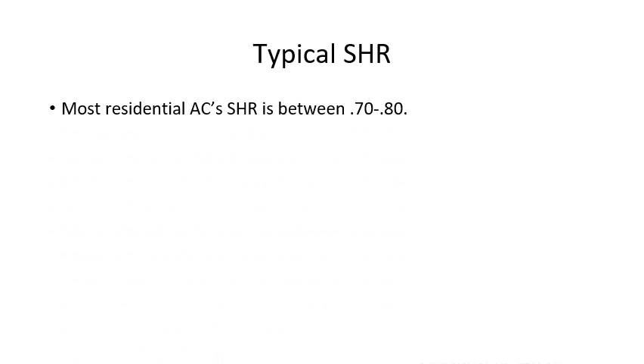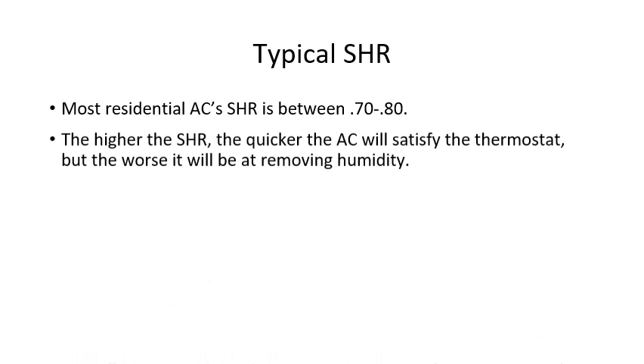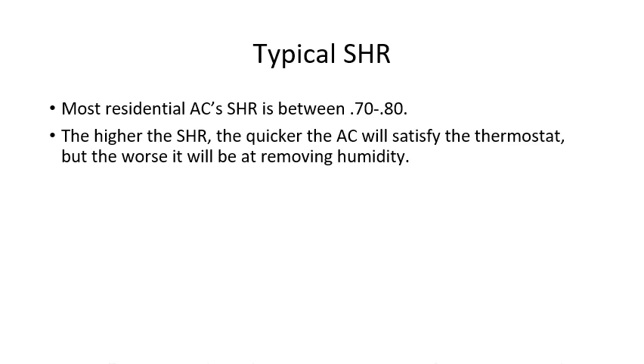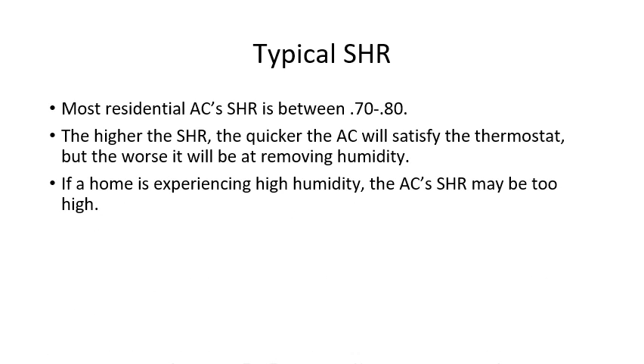Your typical residential air conditioning system sensible heat ratio is between 0.7 and 0.8. The higher the sensible heat ratio is, the quicker that system will satisfy the thermostat, because it's removing more sensible heat than latent heat — it's taking temperature away from the house. But it won't be very good at removing humidity. So if a home is experiencing high humidity, that may mean the AC's sensible heat ratio is too high — it's satisfying the thermostat before it can run long enough to remove humidity.